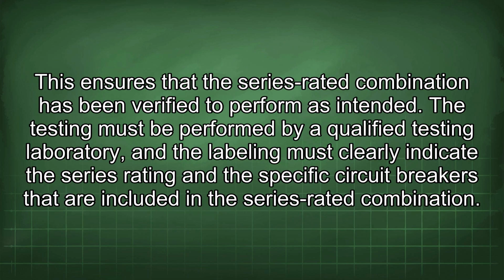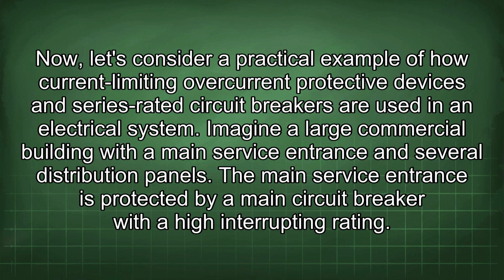This ensures that the series-rated combination has been verified to perform as intended. The testing must be performed by a qualified testing laboratory, and the labeling must clearly indicate the series rating and the specific circuit breakers that are included in the series-rated combination. Now, let's consider a practical example of how current-limiting overcurrent protective devices and series-rated circuit breakers are used in an electrical system. Imagine a large commercial building with a main service entrance and several distribution panels.